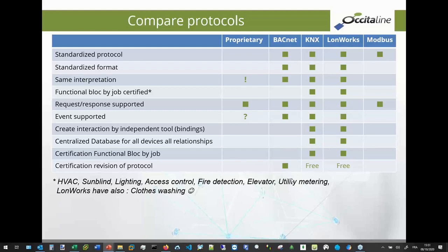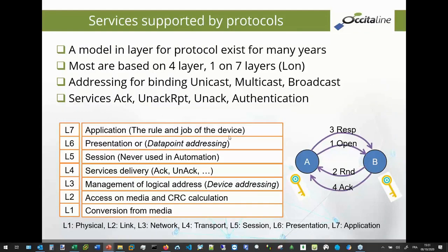In fact, the certification is only based on the revision of the protocol, but it includes some objects inside, but it's not an object dedicated for the HVAC, for example. They have implemented the light, they have implemented some fire detection, but you do not have a large number of functional blocks like we have in KNX and in LON. The certification is defined by the revision of the protocol, and you pay for each revision.